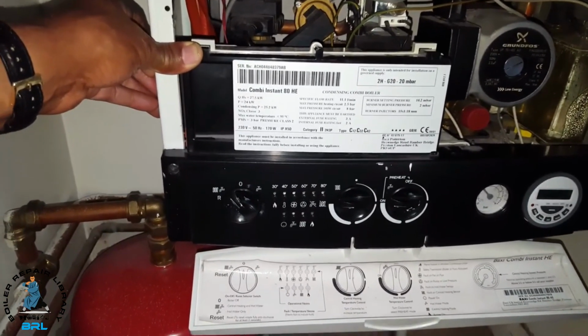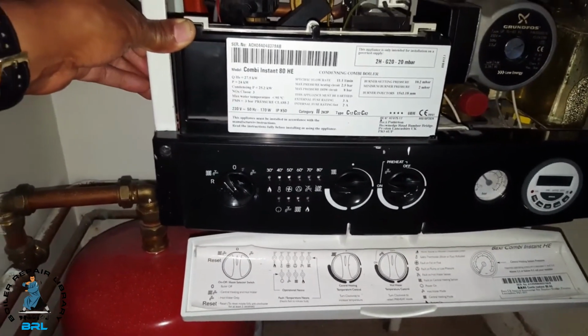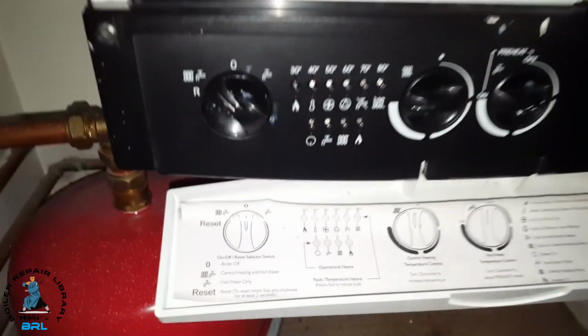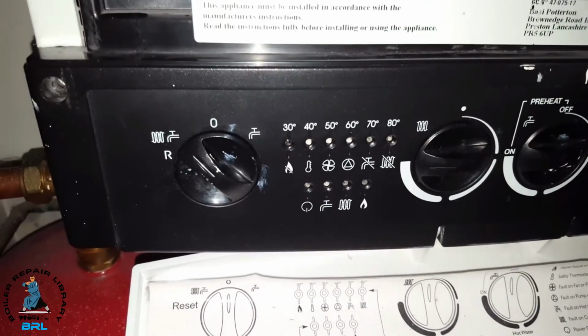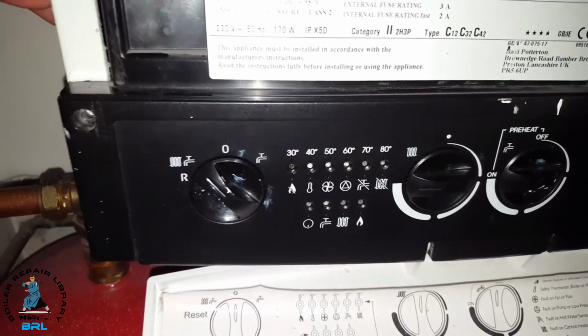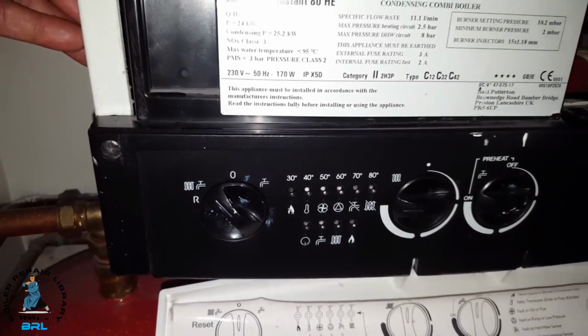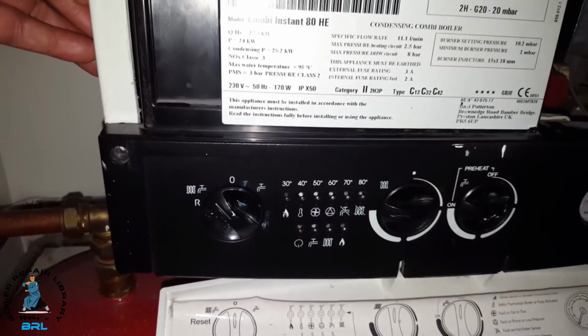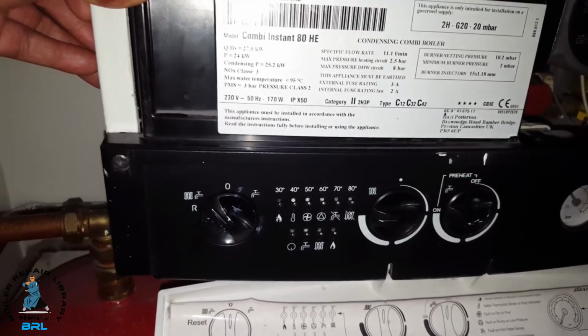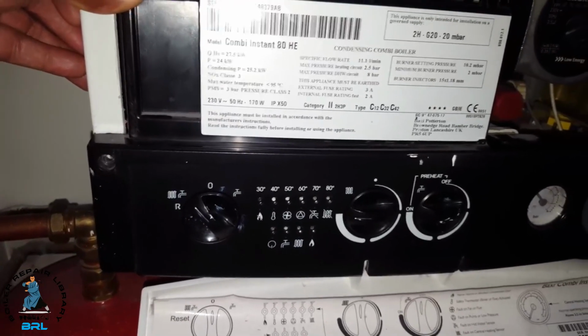Some of the common faults include a PCB fault, and you can see this, the 30 degree light there - if that's flashing, that's usually ignition lockout. You can reset it, but if it comes back on again, that's usually the PCB that's gone faulty. Quite common on these.